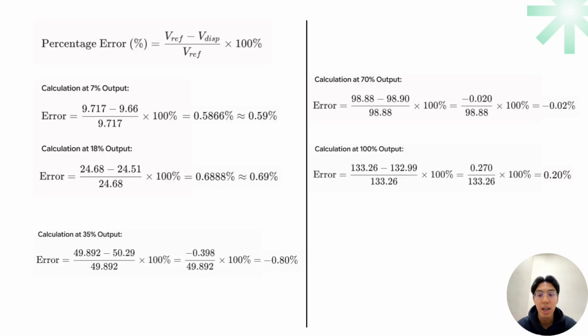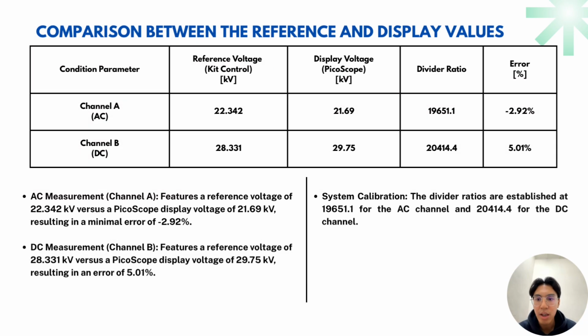0.80%. On the right side, we look at the higher operational limits. At 70% output, the discrepancy drops to just negative 0.02%. Breaking down the math explicitly like this confirms that our data collection is solid and verifiable. It proves that the small errors we see aren't random fluctuations, but rather minor, predictable variations well within an acceptable calibration tolerance.